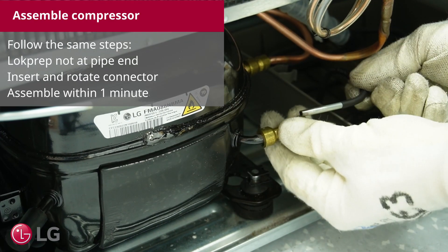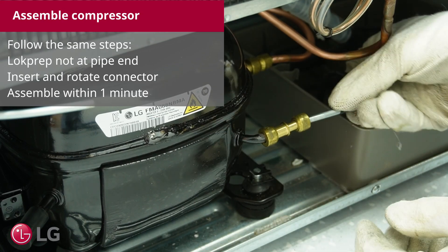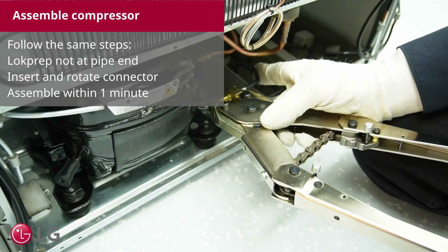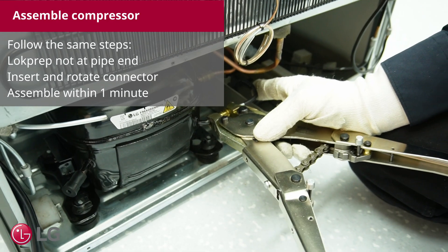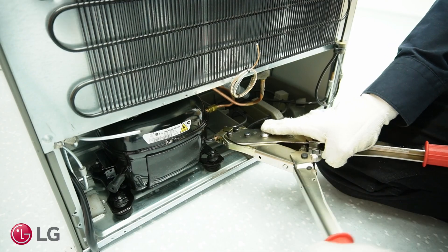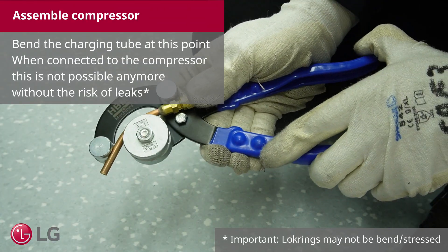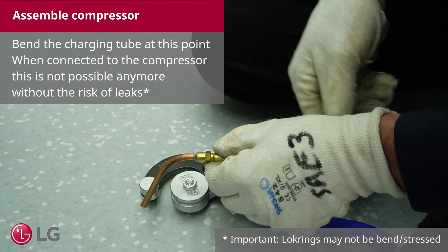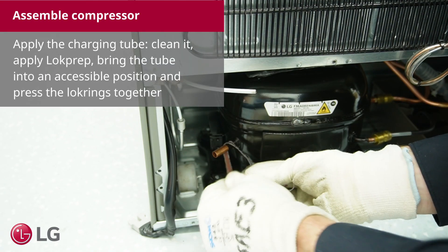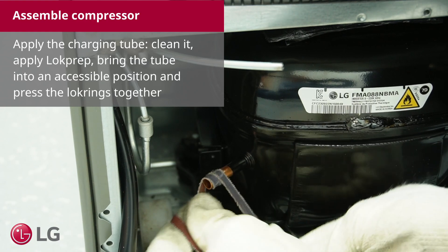Follow the same steps. Do not apply Lokprep at the pipe end. Insert and rotate the connector, and assemble within 1 minute. Bend the charging tube at this point — when connected to the compressor, this is not possible anymore without the risk of leaks. Apply the charging tube, clean it, apply Lokprep, bring the tube into an accessible position, and compress the lock rings together.